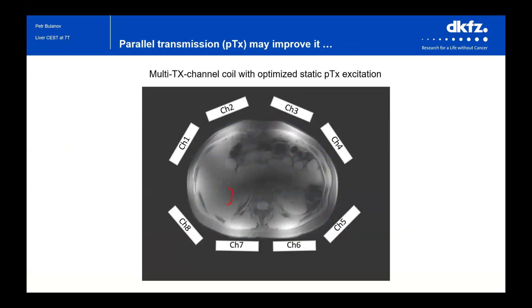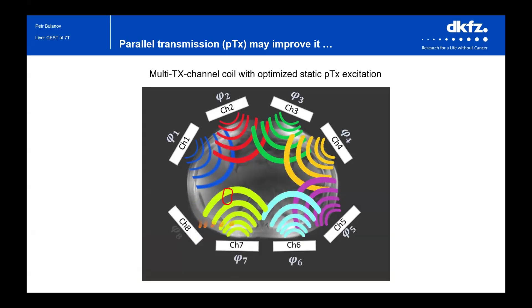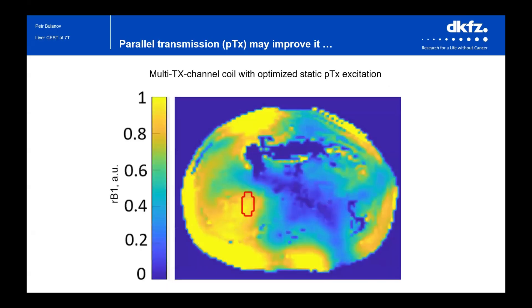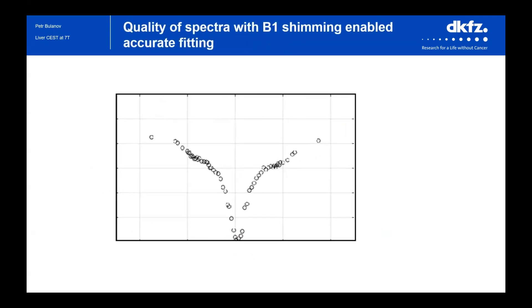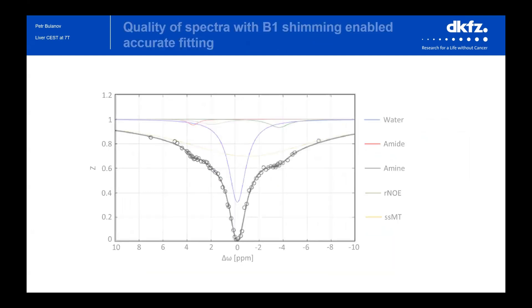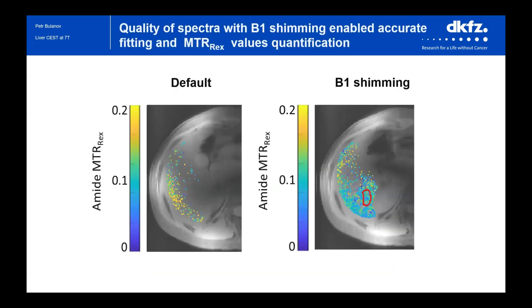we can optimize our signal in some desired region by changing the phases of each individual coil element, which gives us much higher signal in the desired region and spectra of good quality, which we can approximate and calculate corresponding contrasts.